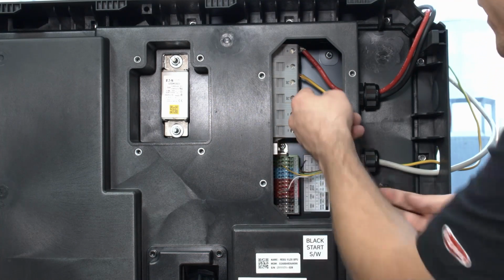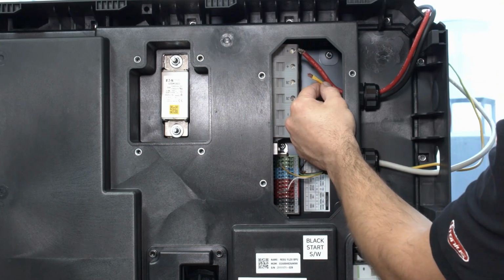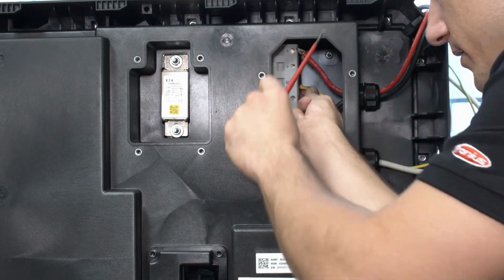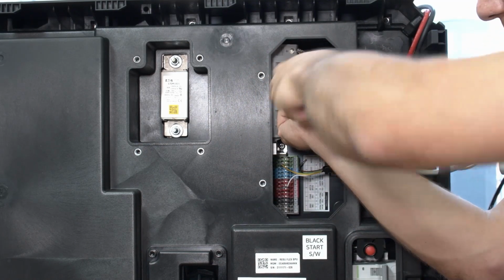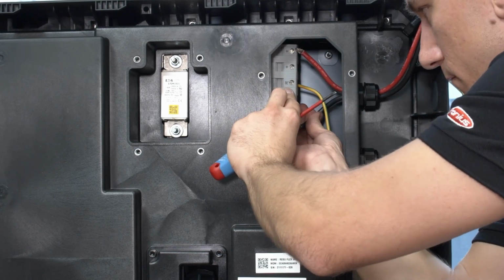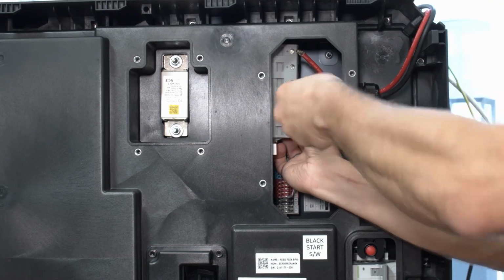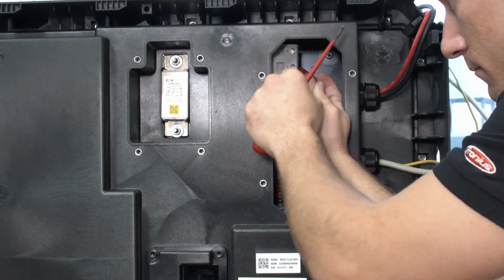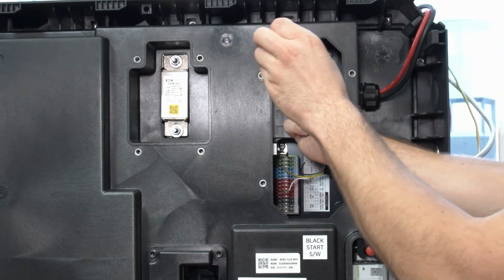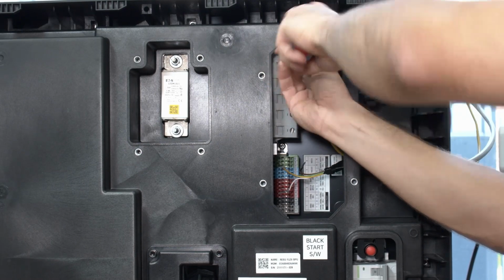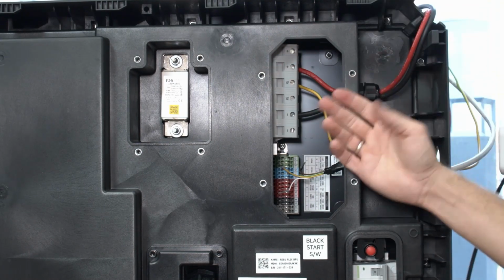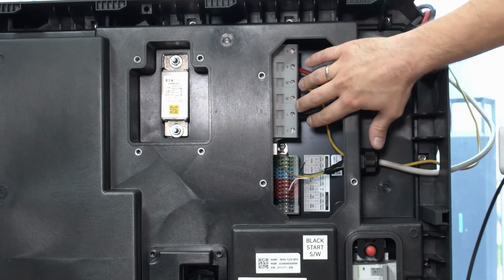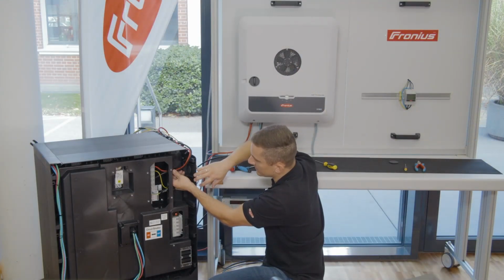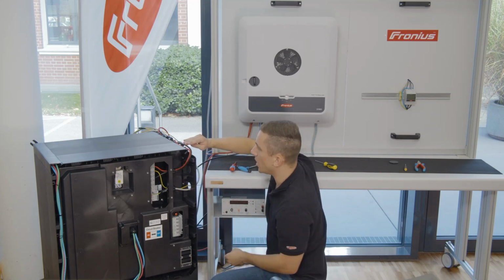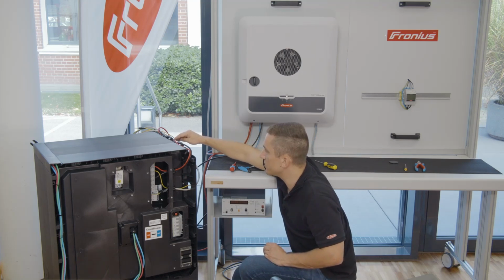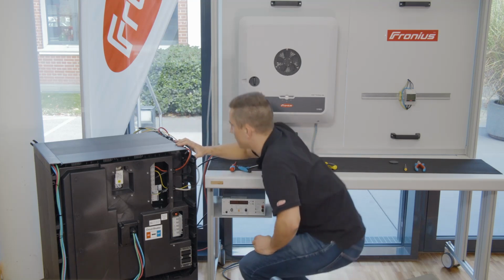So all we want to do now is to cable the battery system, and therefore we take our screwdriver and do the cabling on the battery system. After installing the DC cables to the battery system, you can go with the DC cables through this PG clamp on the right hand side and then exit the battery system on the top. So here you can put your cables on the top of the battery system and directly go to the PV inverter afterwards.